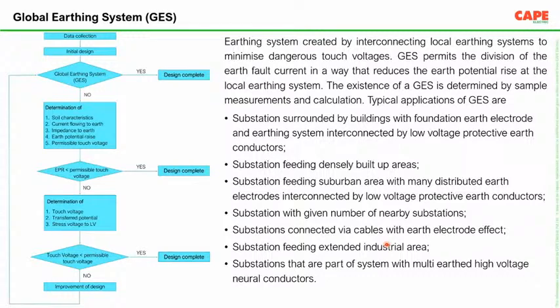The new method of earthing is called the global earthing system. What do we mean by global earthing system? Global earthing system: an earthing system created by interconnection of local earthing systems to minimize dangerous touch voltage. So basically, the earthing systems of low voltage, extra low voltage, and high voltage systems in a typical area are all interconnected in such a way that there is no touch voltage, or touch voltage doesn't exist. This is called the global earthing system.